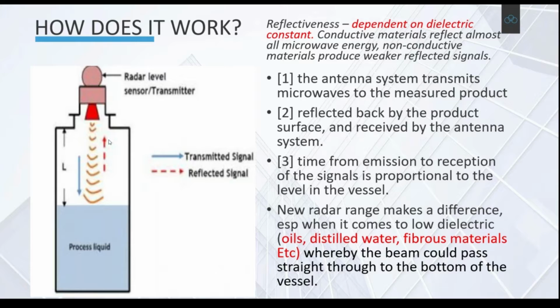So in the legacy versions of the radar, they had trouble where it wouldn't read through, it would shoot through down to the bottom of the tank and reflect up, ignoring the actual surface of liquid in there. The newer range that we've got does make a key difference. There are things like oils, which are less than 5 DK, that weren't always picked up by the older radar. There's also fibrous materials - you could have wool, even cotton candy, or certain funny solids that would absorb the reflections. But we're going to tackle that later as well.